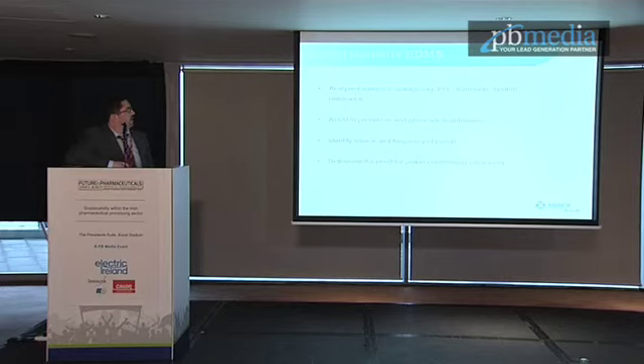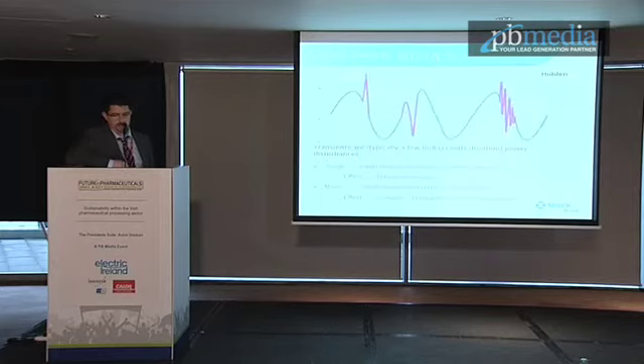Added benefits: harmonic analysis assisted in preventive predictive maintenance, and we were able to determine the frequency event, and we were also able to size power conditioning equipment. Another benefit here is this should be a continuous sine wave. As you can see here, we've got surges from equipment, and 80% of this type of interference is generated within a production facility. It's not actually coming from the electricity supply. Another example of graphs that were taken from the system shows voltage sags and swells from inrush of motors in the area.